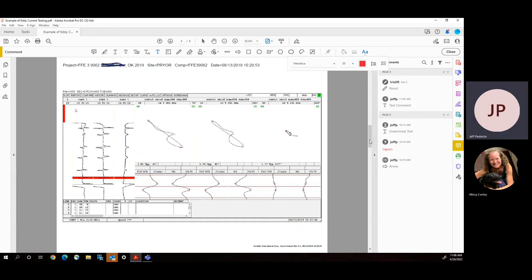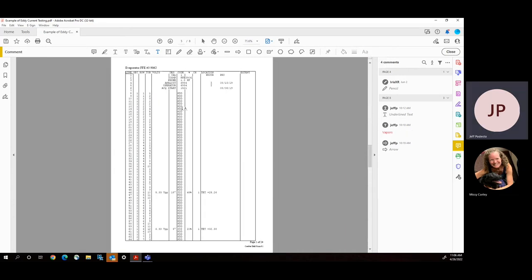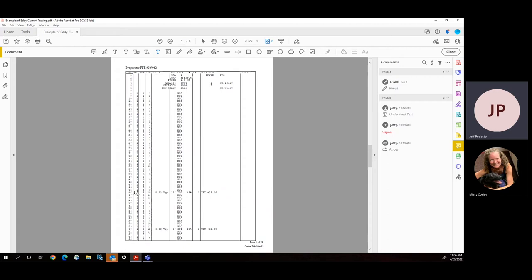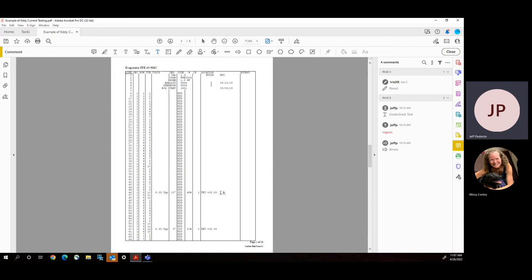That information gets converted into a table, something like this, where each one of the tubes is analyzed. And then if a tube is good and it seems to have no degradation, it'll be given an NDD certification. If it has some kind of failure, it'll explain what that failure is. It'll give us a percentage of what failure. We have a 45% failure. That means that we've got some type of indent or impact to the tube, and 45% of the thickness is gone in that particular area. And we have a depth. This is what's really important, is that from the top of the evaporator, 26 feet down, that's where the failure point is on that particular tube.